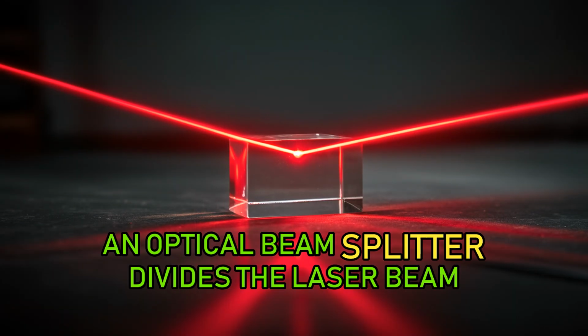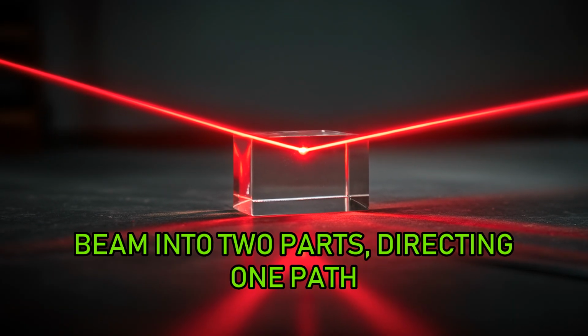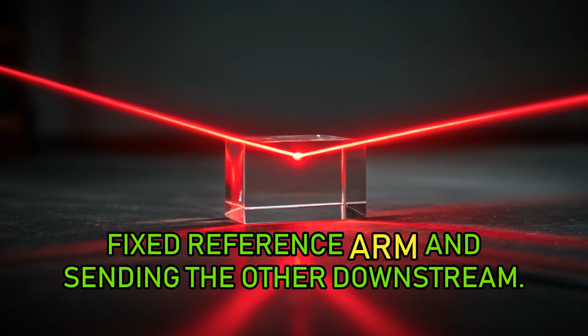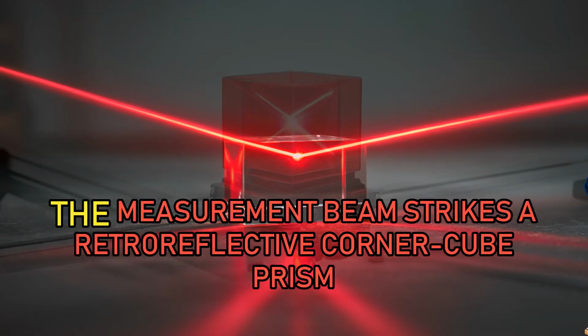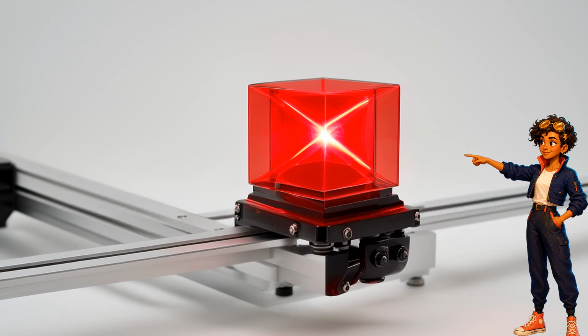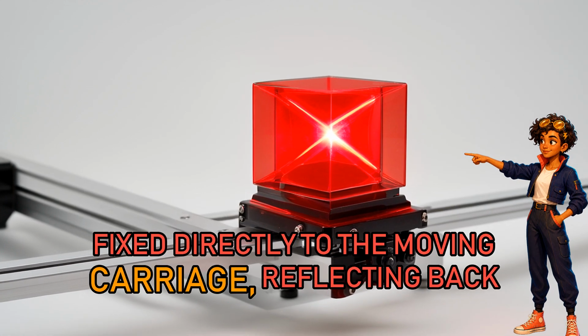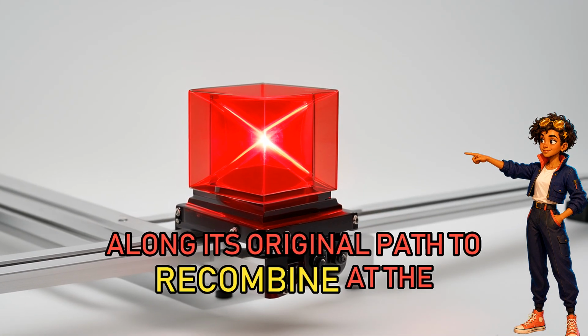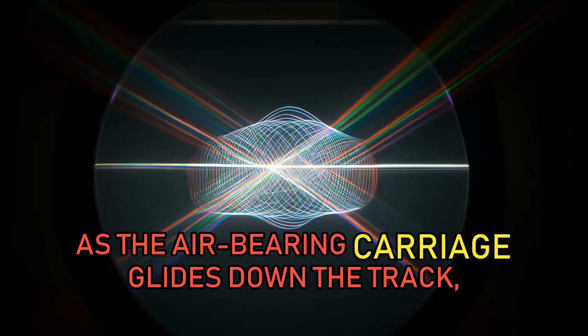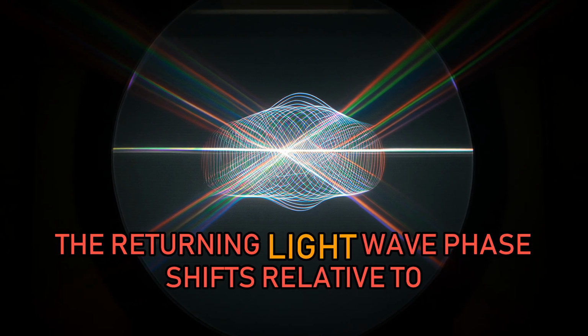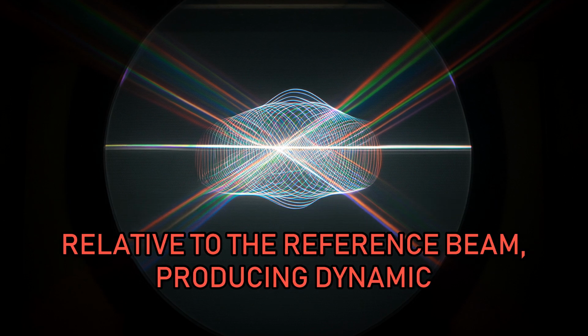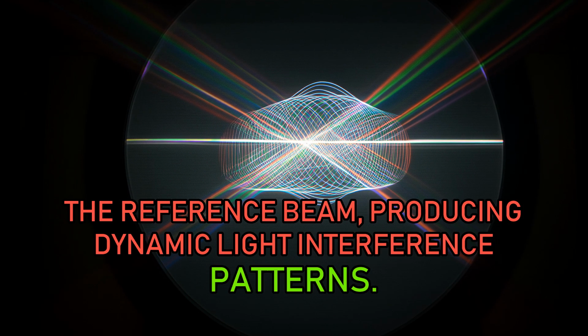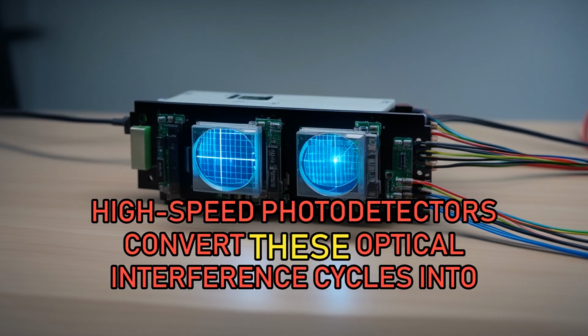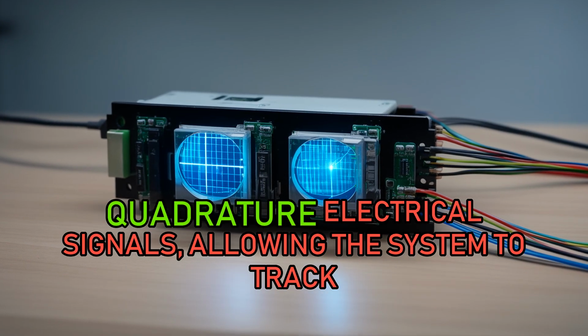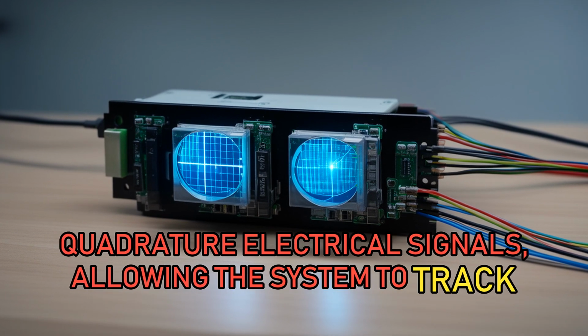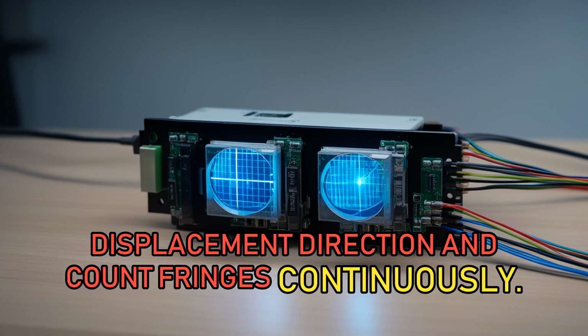An optical beam splitter divides the laser beam into two parts, directing one path into a fixed reference arm and sending the other downstream. The measurement beam strikes a retroreflective corner cube prism fixed directly to the moving carriage, reflecting back along its original path to recombine at the splitter. As the air-bearing carriage glides down the track, the returning light wave phase shifts relative to the reference beam, producing dynamic light interference patterns. High-speed photodetectors convert these optical interference cycles into quadrature electrical signals, allowing the system to track displacement direction and count fringes continuously.